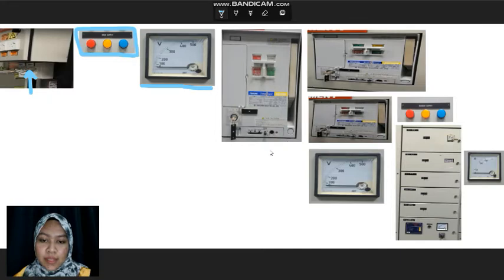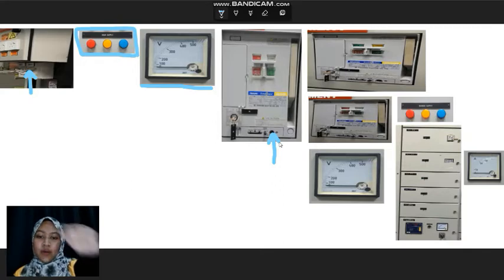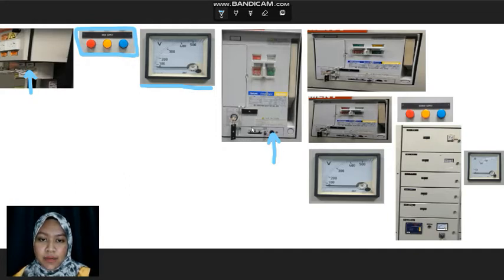Now we must connect the air circuit breaker to the bus bar. First, we take the charging handle inside the ACB compartment and insert it inside the slot here. Then we turn the charging handle clockwise until the air circuit breaker is in connect position. After the air circuit breaker is connected to the bus bar, we must turn it on.